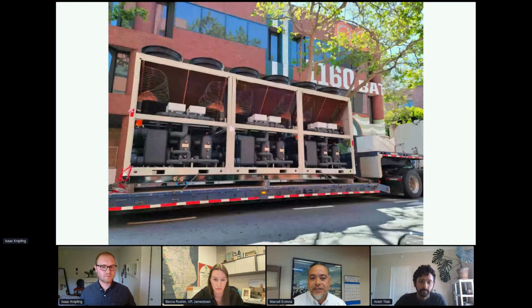Yeah, no, that's correct, Becca. When you're doing an air cooled system, our system pretty much called for an air cooled heat pump, and it produces a lower intensity heat compared to a gas fired boiler. So about 125 degrees of heating water versus 180 degrees. You definitely want to make sure you get with your mechanical engineer and make sure that the existing equipment at the zone or floor level is adequate for this new system.